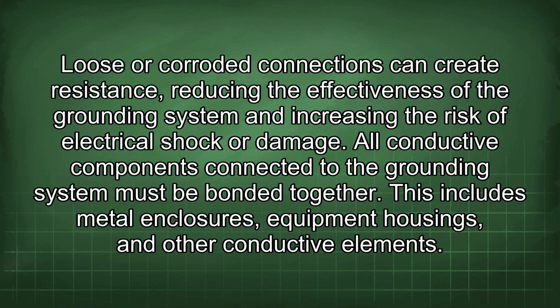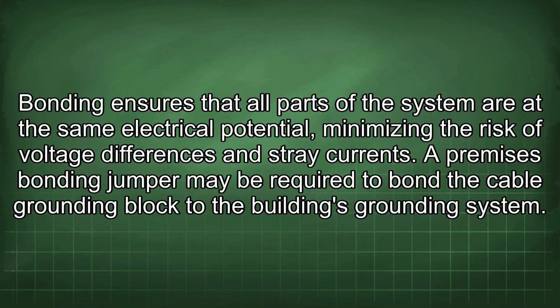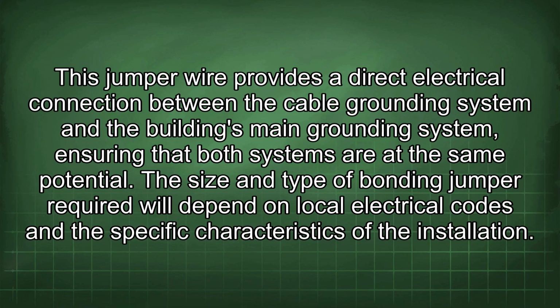This includes metal enclosures, equipment housings, and other conductive elements. Bonding ensures that all parts of the system are at the same electrical potential, minimizing the risk of voltage differences and stray currents. A premises bonding jumper may be required to bond the cable grounding block to the building's grounding system. This jumper wire provides a direct electrical connection between the cable grounding system and the building's main grounding system, ensuring that both systems are at the same potential.